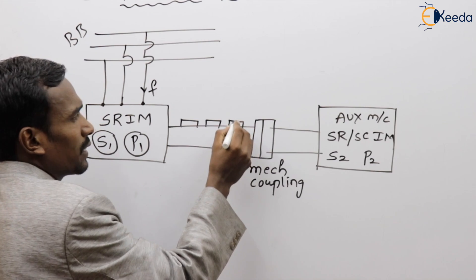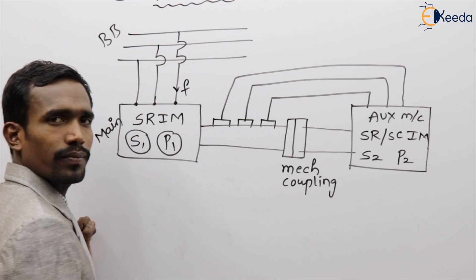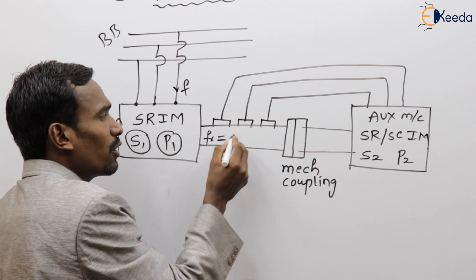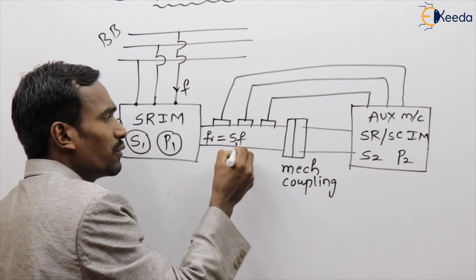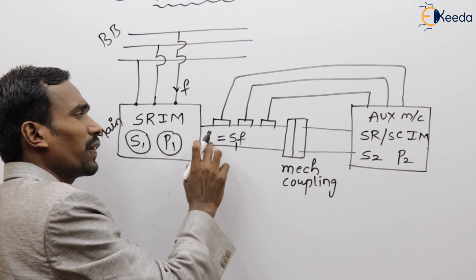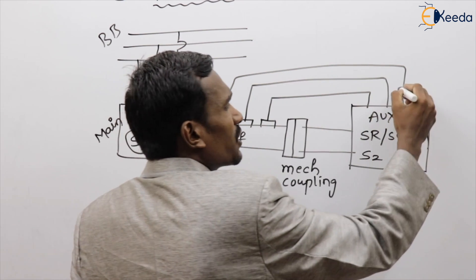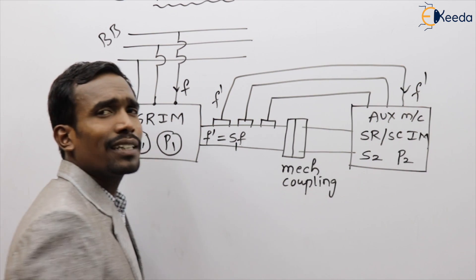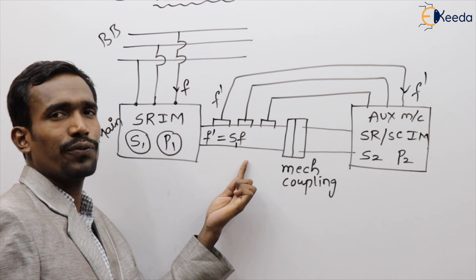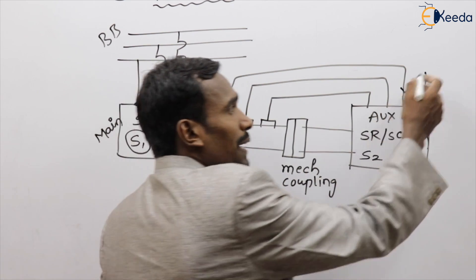The main machine has slip rings, and these slip rings supply power to the auxiliary machine. The rotor frequency of the main machine is F dash, which equals S1 × F. This rotor frequency F dash becomes the supply frequency of the auxiliary machine.